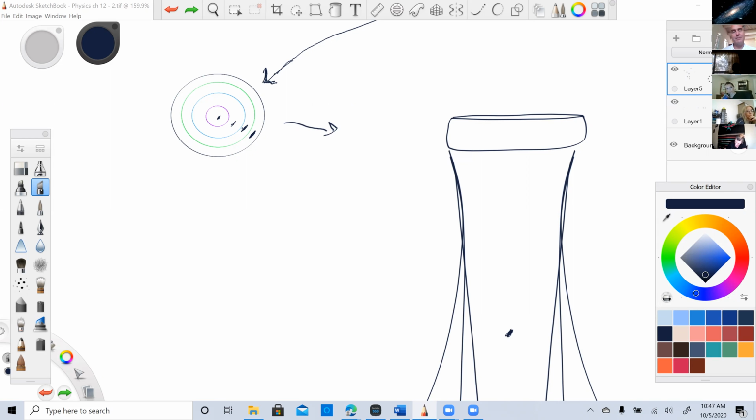There's no left to right phasing. You can't do it. You can do outside in, which is focusing. So these guys can electronically focus, but if you're going to steer them, they have to be attached to a mechanical transducer.